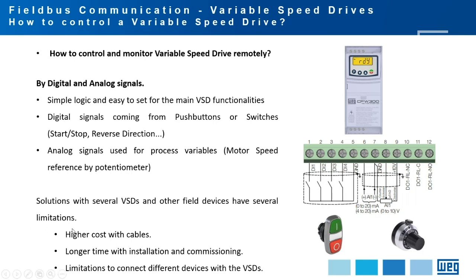These limitations include higher cost due to several digital and analog cables connected to each variable speed drive, longer installation and commissioning time, and limitations concerning the available terminals on the drives. For example, the CFW300 WEG variable speed drive has only 12 terminals available. When deep control and monitoring is required, 12 terminals will not be enough.